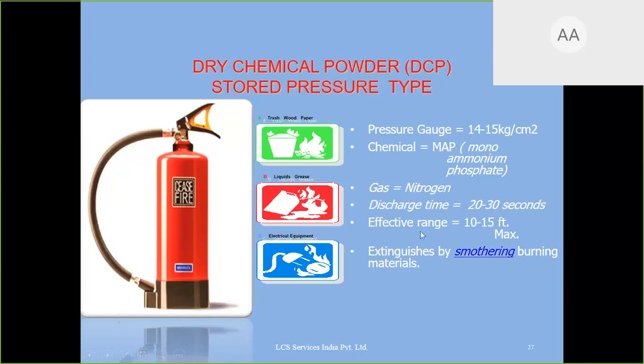Discharge time 20 seconds, effective range 10 to 15, and it controls the fire by the smothering method, that it will put powder on the flame so that the fire does not have contact with the air where it gets oxygen, and if the fire does not get air, the fire will be consumed. Fire needs oxygen to burn, which is in the air. If fire does not get any air, it will not get oxygen, and fire cannot take place without oxygen. For fire we have 3 elements. It is a must: oxygen, fuel and spark. All 3 things must be there together, then only fire will be there. If one thing happens after the other and then the third, there will be no fire.